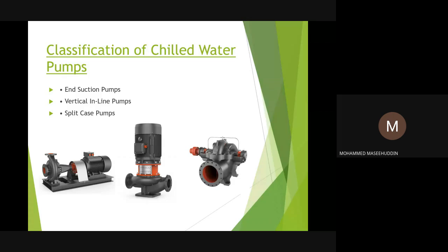These types of pumps are mostly used in the secondary circuit because of the pressure rating. The nominal pressure, the casing pressure of these pumps, starts from 16 bar and goes up to 30 bar. It means if, let's say, a typical building has 80 floors and we need to pump it through the roof and to the last FCU, and the head is about 150 meters, this can easily handle that because it can handle up to 30 bar of nominal pressure.